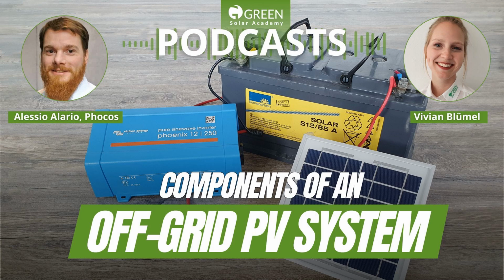Okay. So what would you look out for when deciding for an inverter? When would you take an MPPT charge controller? Yeah, sorry, a charge controller. Well, I've kind of mentioned those points. When the PV voltage and the battery voltage are significantly different, right? Because I want to use 60 cell modules on a 24 volt or on a 12 volt system, or because I'm working with a very big system, so I want to have a higher PV voltage because it means I have fewer strings, I don't need combiner boxes, things like that. So whenever the PV voltage is very different from the battery voltage, that's when we almost definitely need an MPPT.